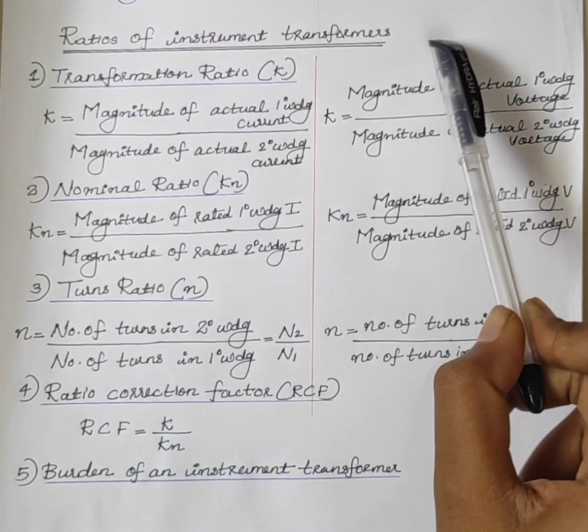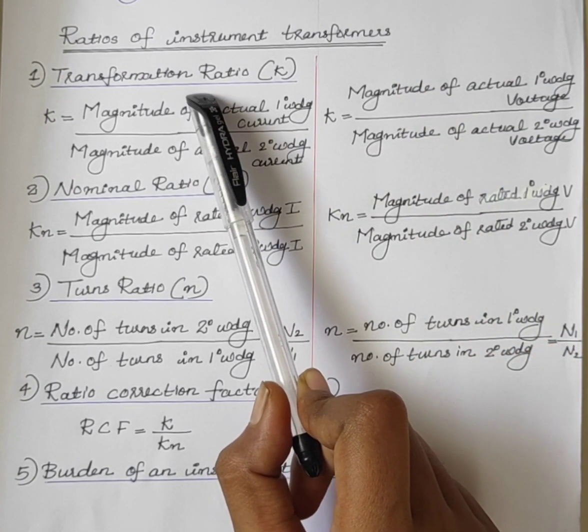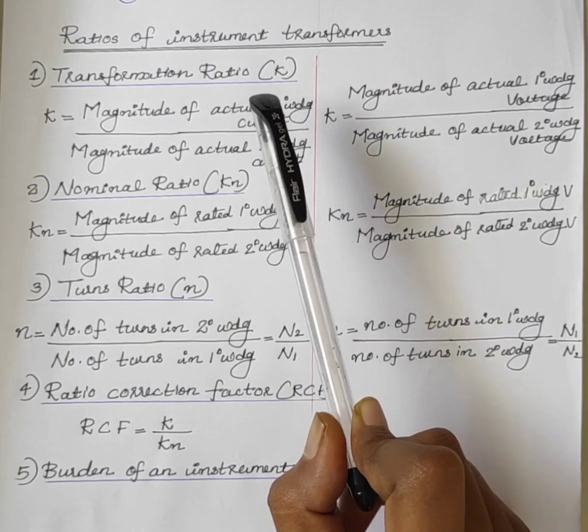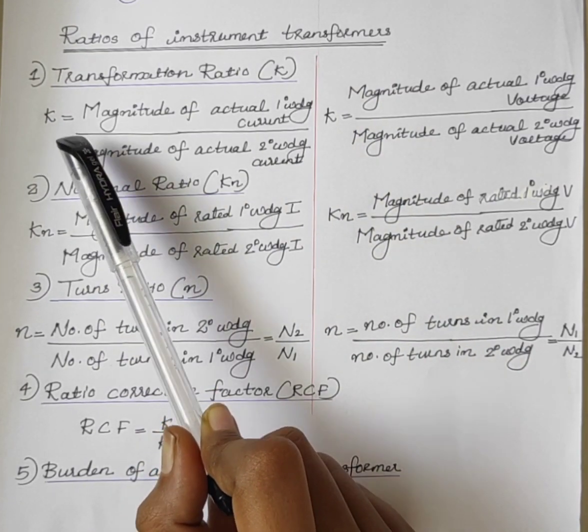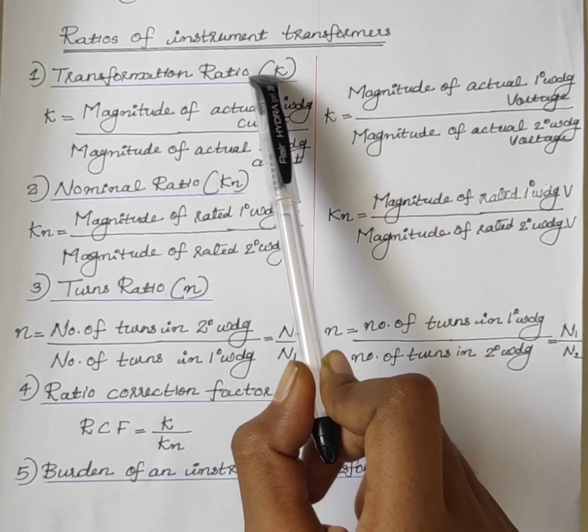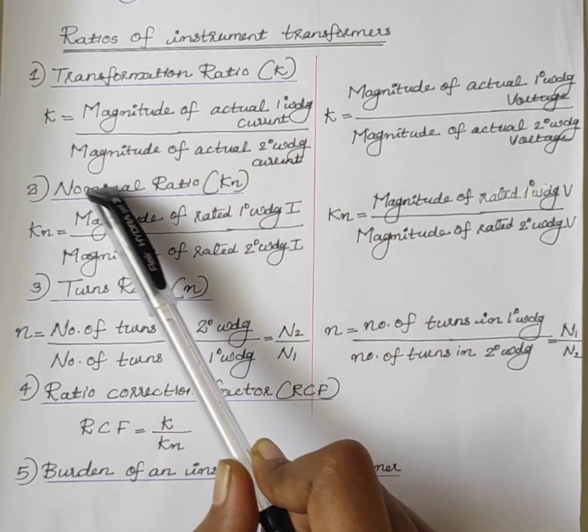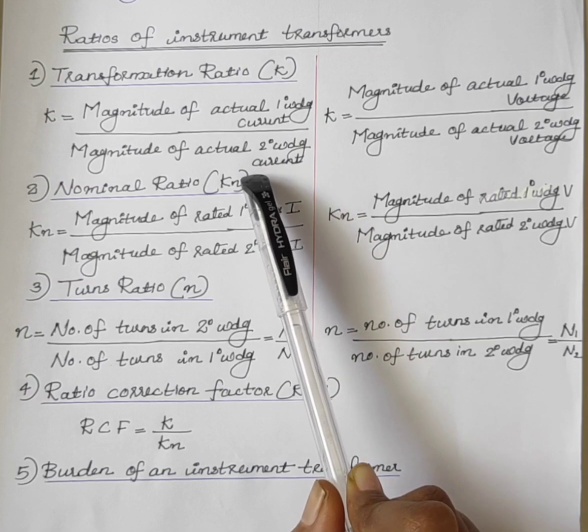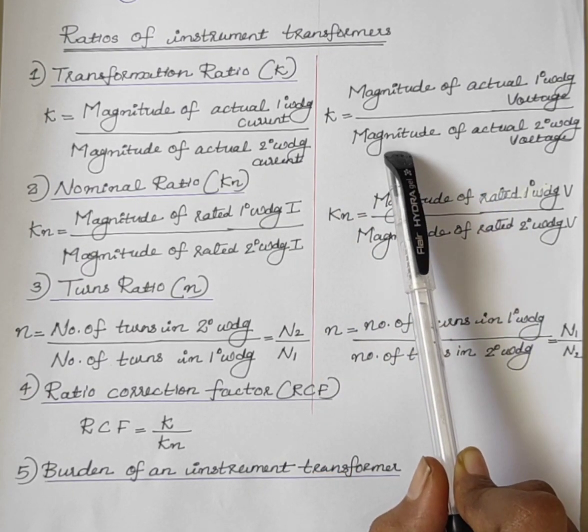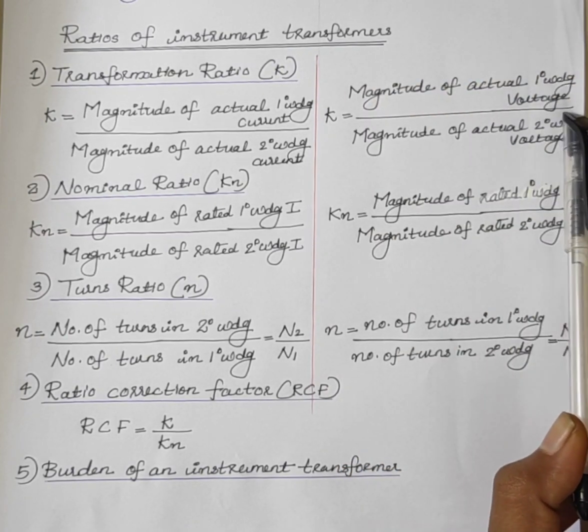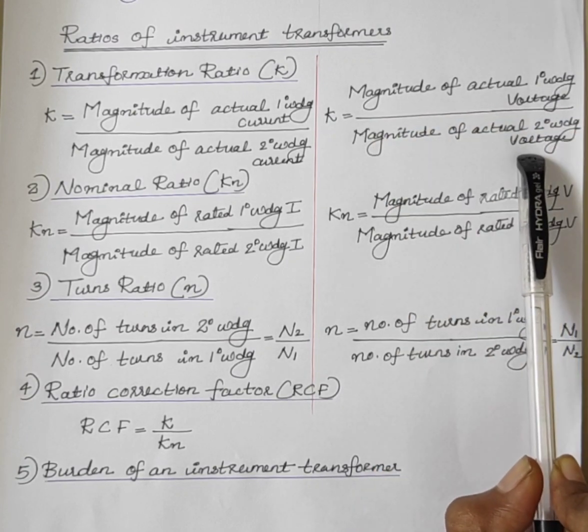Next, we will see the ratios of instrument transformers. The first one is transformation ratio, represented by K. In a current transformer, transformation ratio K is equal to the ratio of the magnitude of actual primary winding current to the magnitude of actual secondary winding current. In the case of a potential transformer, it is the ratio of the magnitude of actual primary winding voltage to the magnitude of actual secondary winding voltage.